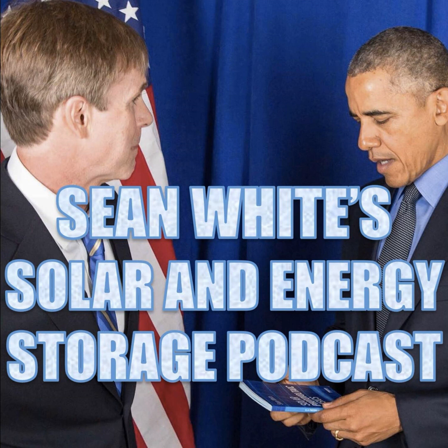And also a really good, interesting one too is blind spot. So do another Solar ABCs search for the blind spot, and you can find out one of the reasons why we are not using these old style grounded inverters, because they are not as sensitive at detecting ground faults, and they are also more expensive to make because they have transformers in them. But some of these older systems out there are getting retrofitted to be safer.